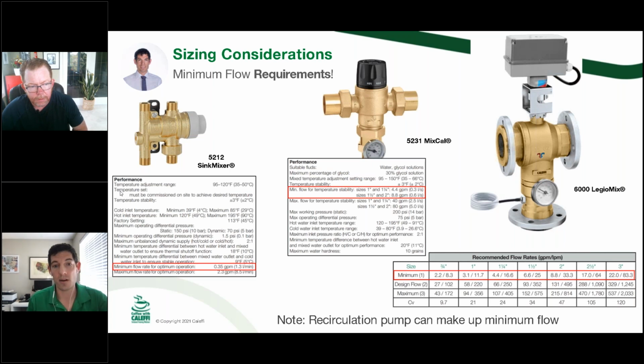One big note here is that if you're looking at a commercial job and you're selecting an 1.25" valve or something like that, the recirculation pump does count towards that minimum flow rate. So if you think, well, for an 1.25" valve, 4.4 is a little bit higher than that single unit turning on a shower or something like that, you're counting the recirc pump as part of that to get to that number. So that should be more achievable if it looks like 1.25", 4.4 is too small for your minimum.